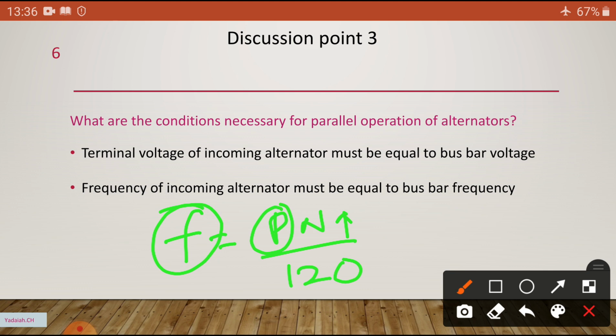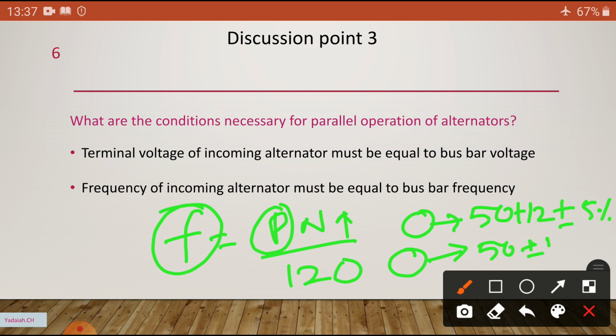The already existing system generates at 50 Hz plus or minus 5%. Similarly, the incoming new one should be run such that it also produces 50 Hz plus or minus 5%. That is the meaning of these two matching, and it depends upon the speed of rotation, which can be controlled with the help of the governor system.